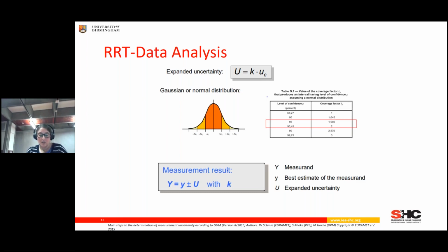Also, another note: this approach is just calculating the empirical or experimental uncertainty of the results. That could lead to precise results, but they can be far from the real one. And for that, what we should do, and it's one of the next steps, is to have the uncertainty of the systematic error that comes from the equipment, which is done through the use of standard materials.